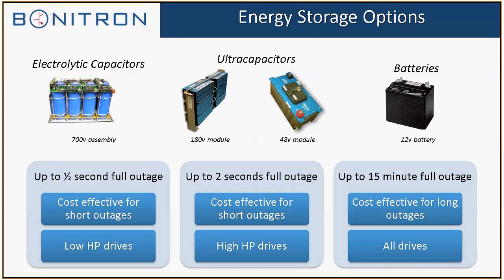Our standard units are 4 minutes and 15-minute full outages, and we can derate up to any time you want, but then it gets much less economical the longer the time. So when you have to derate something by half, meaning if you have a 15-minute ride-through, you would derate a 4-minute ride-through for half of that kilowatt requirement, or for 2 times the kilowatt requirement, excuse me.